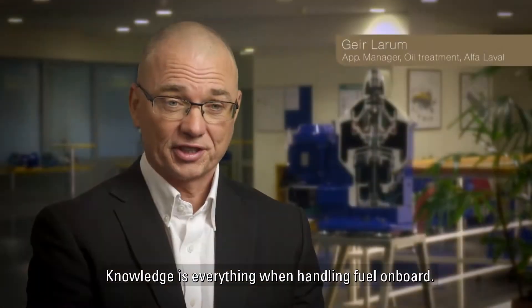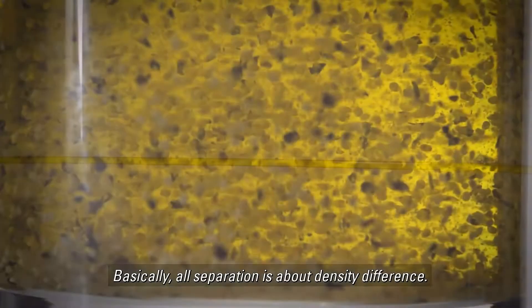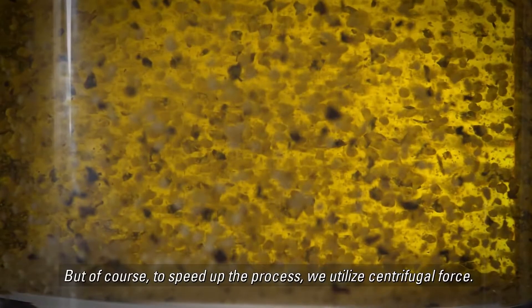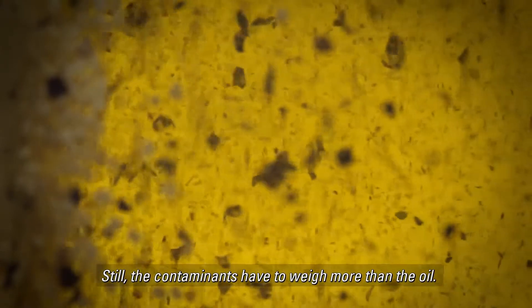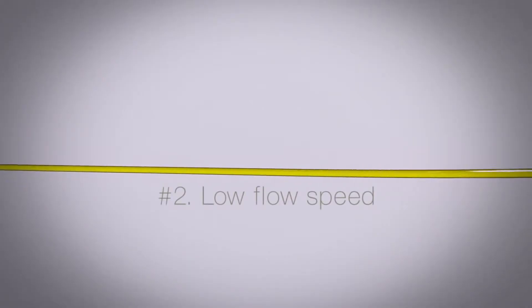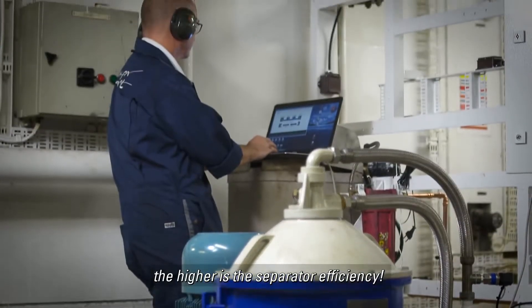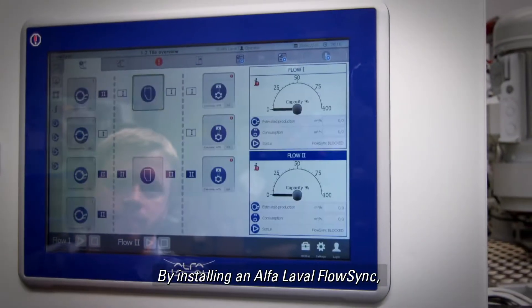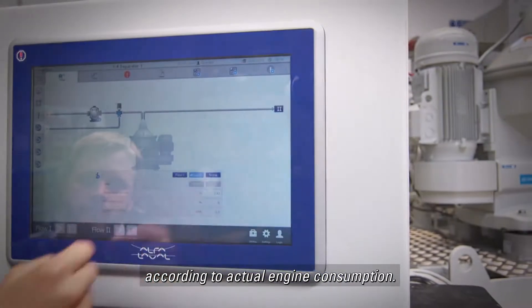Knowledge is everything when handling fuel onboard. Basically, all separation is about density difference. To speed up the process, we utilize centrifugal force. Still, the contaminants have to weigh more than the oil. A major challenge is that the density of some of the cat fines are close to that of the oil. The lower the flow speed through the separator, the higher the separator efficiency. By installing an Alfa Laval FlowSync, you'll automatically optimize separator flow according to actual engine consumption.